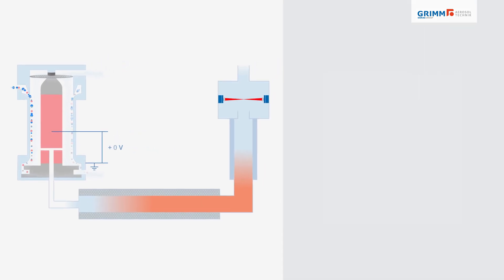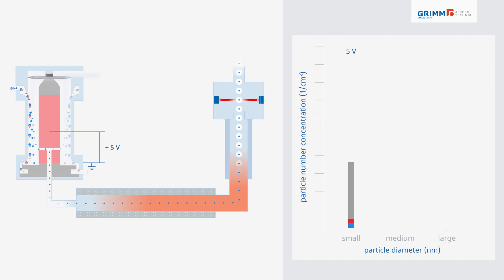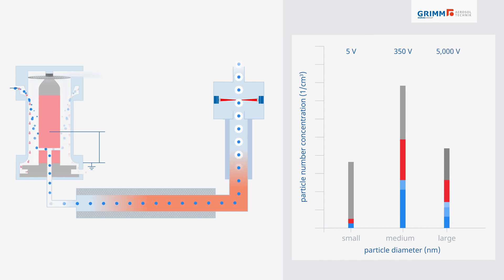The time required for particles to travel from classification to counting assigns the particle sizes to particle concentration. Because only negatively charged particles exit the DMA, the particle count must be corrected for neutral and positive particles. Every voltage scanning cycle results in a preliminary particle size distribution.